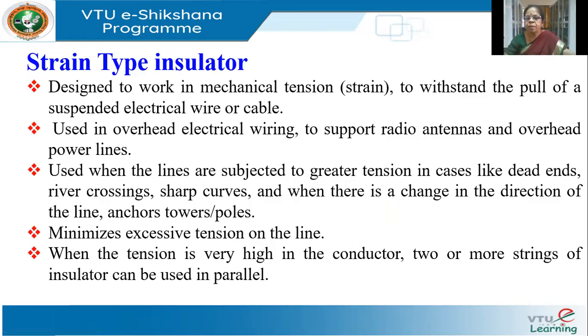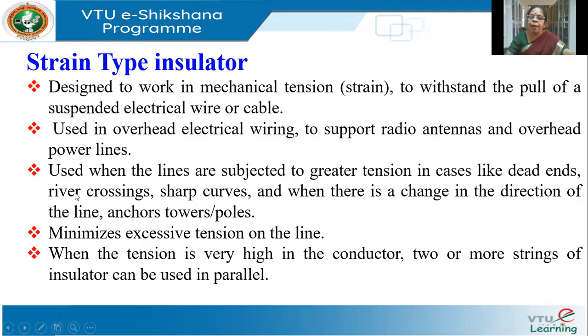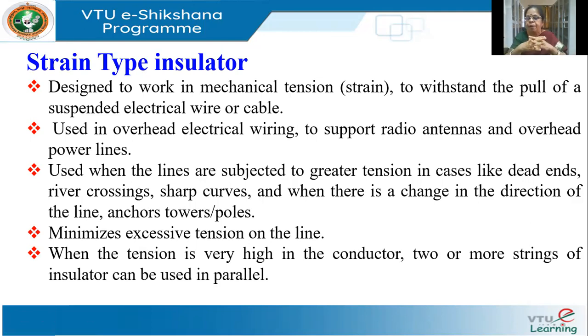Next, we have strain type insulators. These are similar to suspension type, except they are mounted horizontally to withstand the pull of a suspended electrical wire or cable. They provide horizontal support to hold the wires. They are used to either support radio antennas or overhead power lines, and also where the wire or line is subjected to great tension — for example, at a dead end or when there is a sharp bend. They have discs but are mounted horizontally.